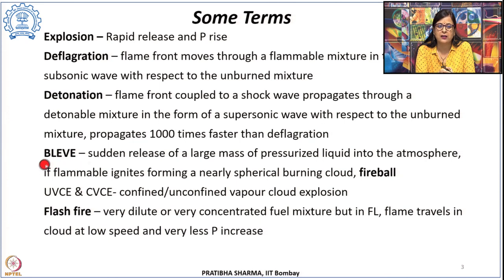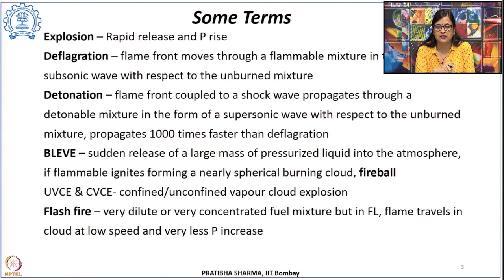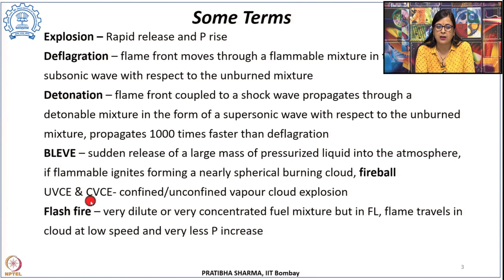BLEVE — boiling liquid expanding vapor explosion — is a sudden release of a large mass of pressurized liquid into the atmosphere, which can lead to two incidents: a fireball or a flash fire. If the flammable mixture ignites and forms a spherical burning cloud, it is known as a fireball. It could be a confined vapor cloud explosion or an unconfined vapor cloud explosion depending upon whether it is confined or unconfined release.